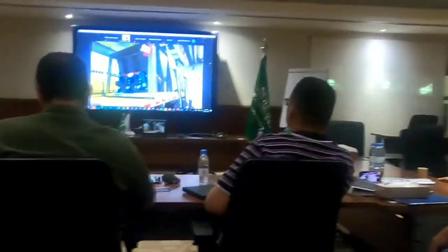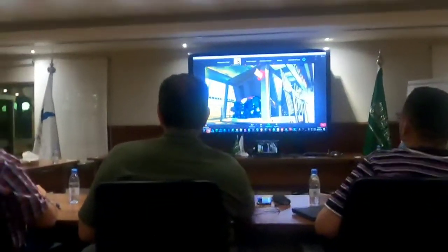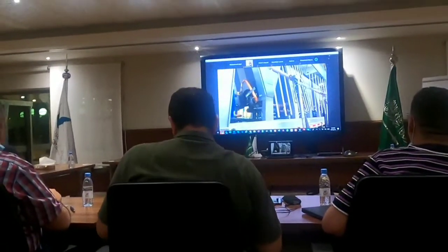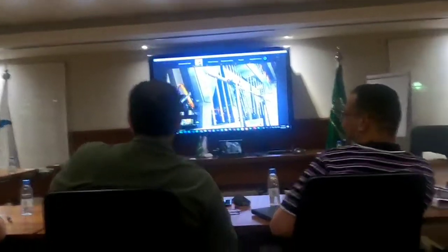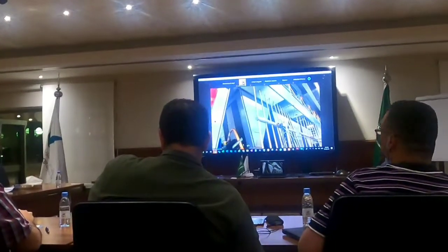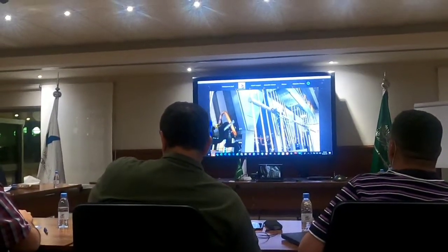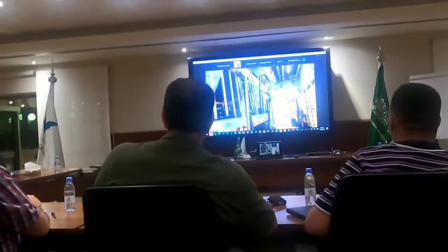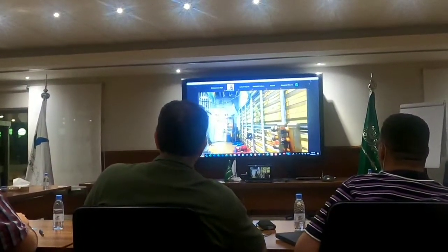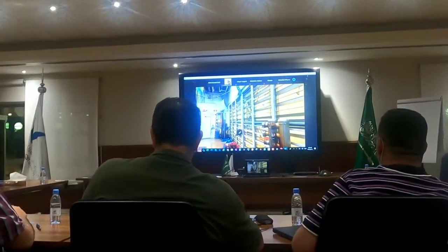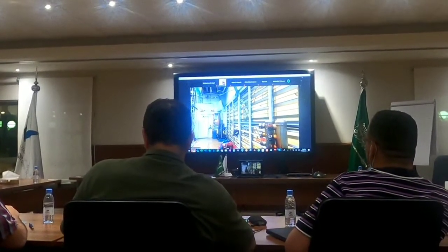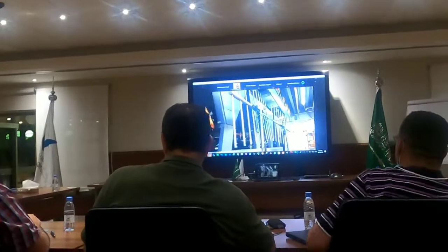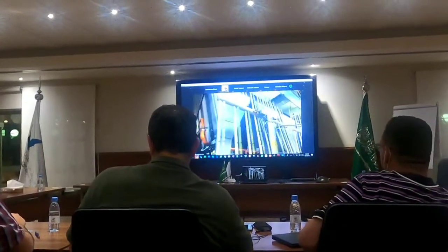Can you guys hear me okay? Okay. Yes, we can hear you. Thank you. You're welcome. He's moving slowly around. We talked about those trees that were on the side of the chiller. I have some still pictures of that. And those are the trees that actually measure the entering air temperatures. So as that air passes through those, it collects the air temperature on both sides of the chiller. And the louvers you see there now is where the air is coming down from the heat exchanger upstairs, back in front of the trees there, and then it passes into inside the chiller where we can make the measurements.